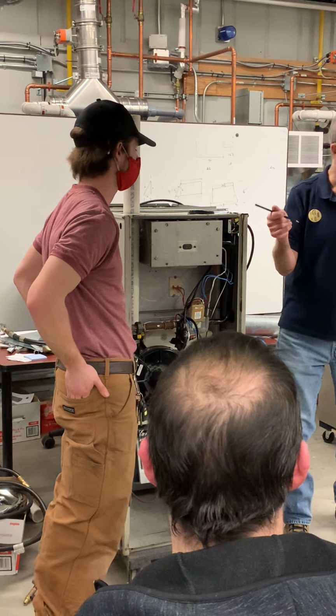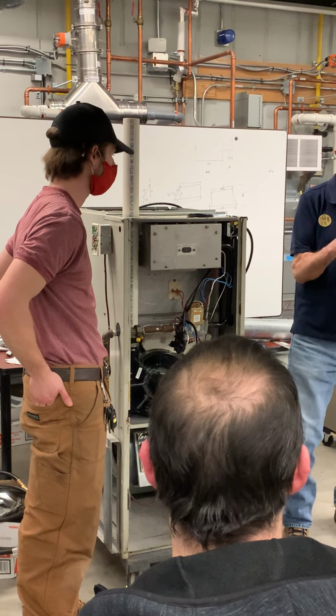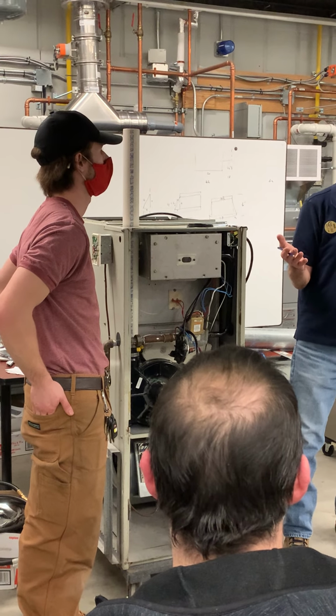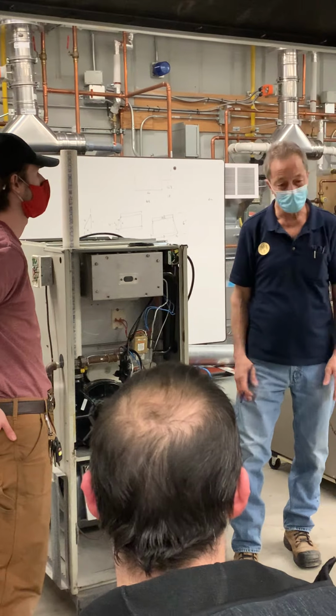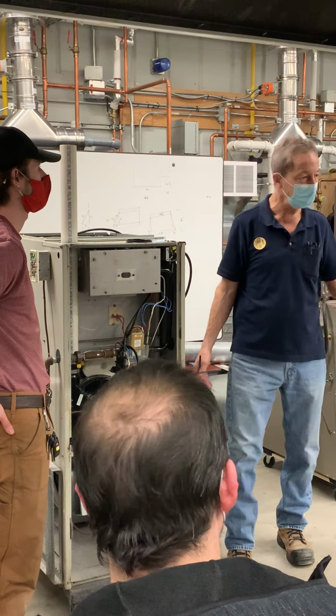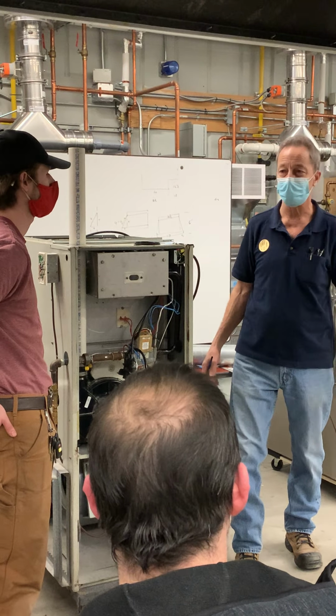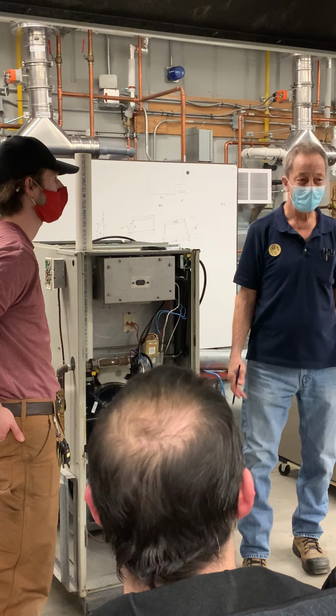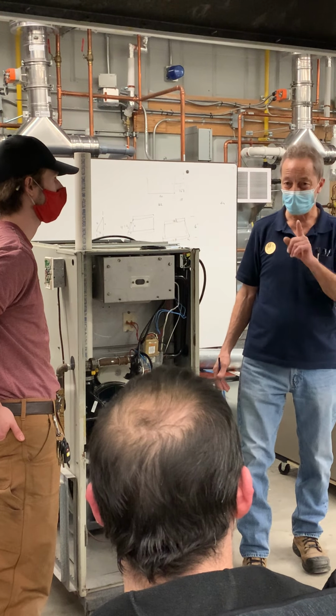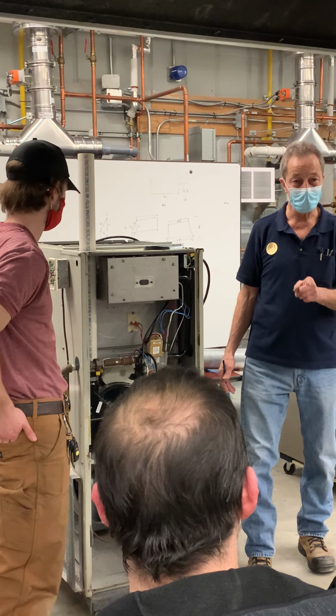90 seconds maybe? It's a 90-second trial for ignition. So it'll go for the 90 seconds, then it's going to shut off. Someone else might think, oh darn, it must be the main gas valve. Main gas valve didn't fire. Must be a defective main gas valve. No, sorry, bud. It tried for 90 seconds, it didn't see the flame, it didn't sense the flame, it shut down.